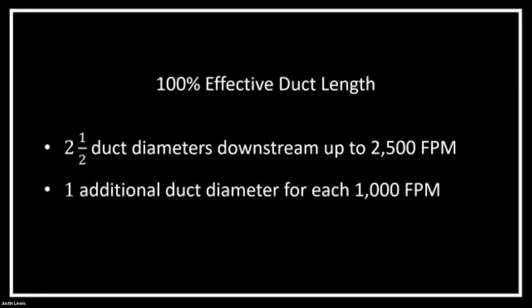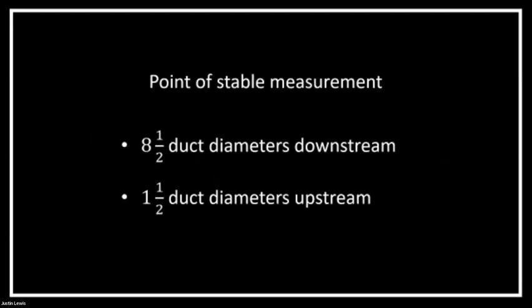Accurate measurements are another matter. Dwyer, along with other manufacturers, outline a requirement for 10 straight uninterrupted duct diameters for accurate use of their instruments. To put that in perspective, a 20-inch by 12-inch supply duct would require 175 inches, or 14.5 feet, of straight duct to perform a textbook traverse reading. Now, this is available about 0.003% of the time.